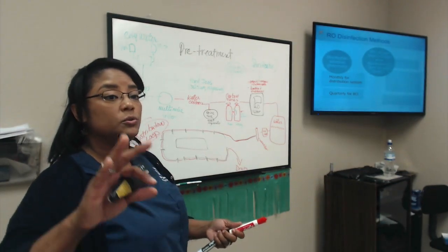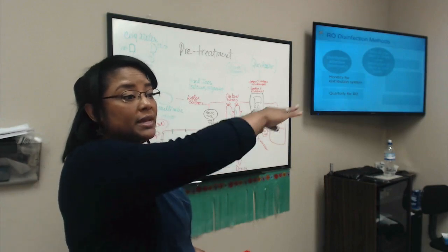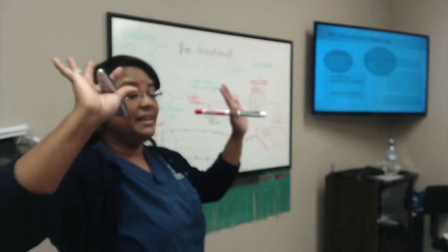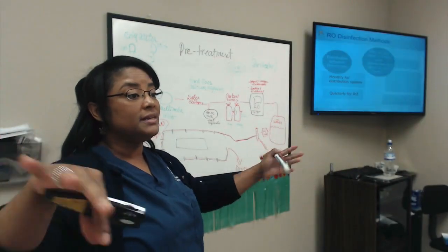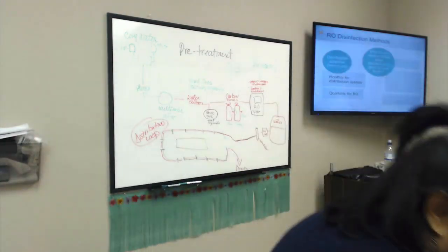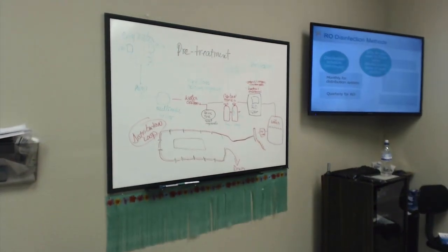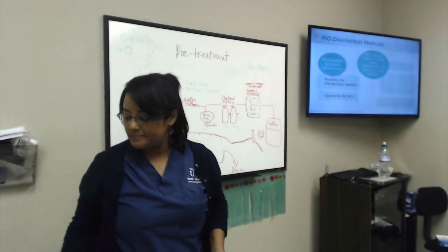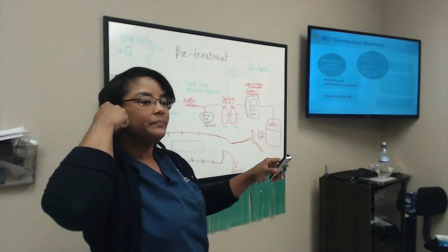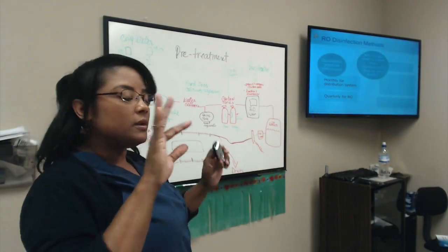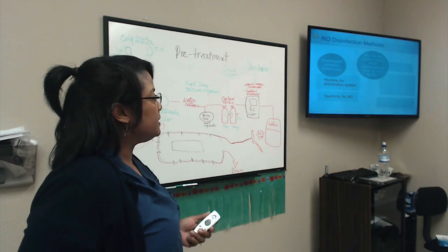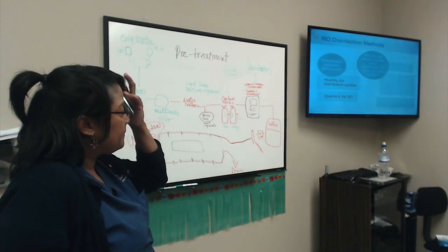Because what they do is something similar to pouring bleach through the entire system, letting this bleach dwell, and then rinsing everything out. Does that make sense? Questions about it? It has to be done when there's no dialysis treatments, when there's no patient there.